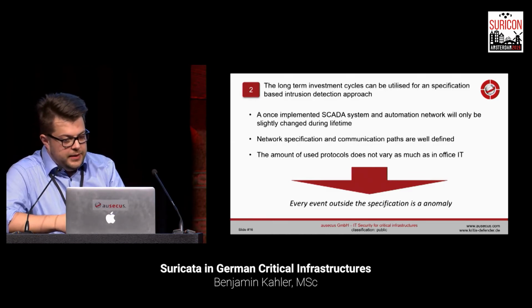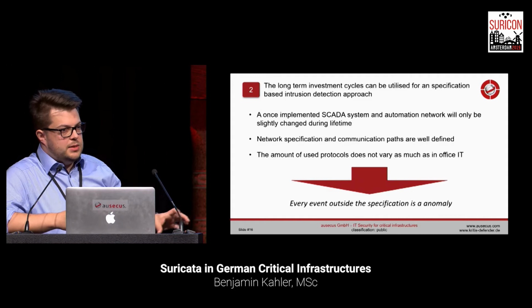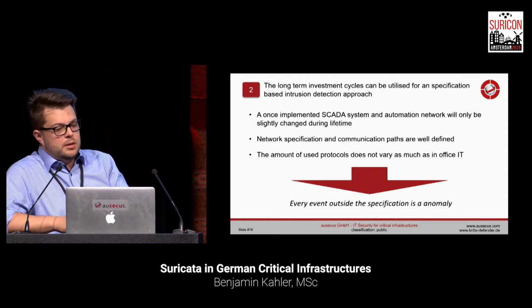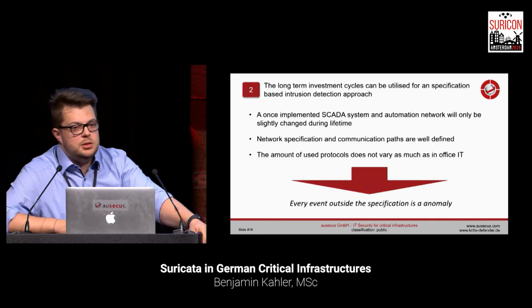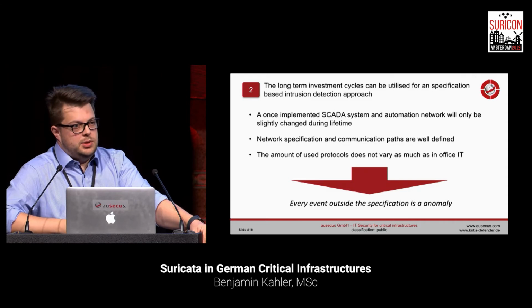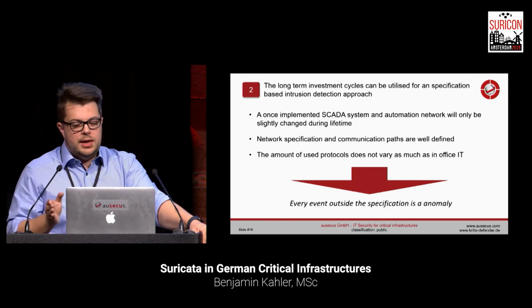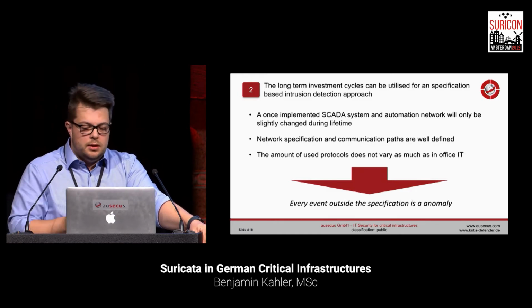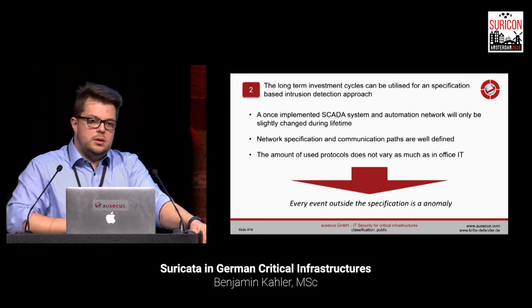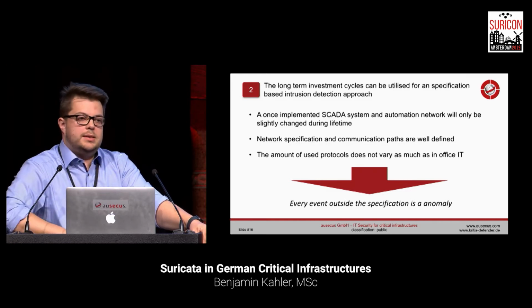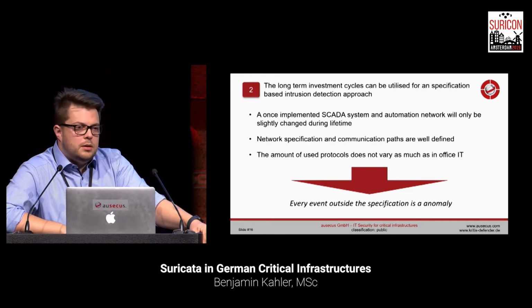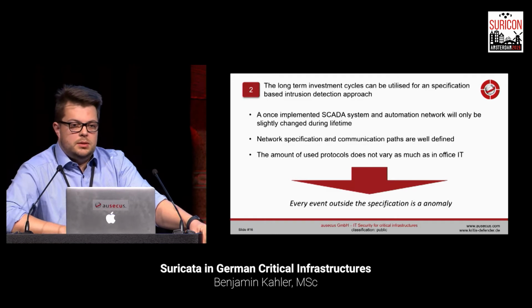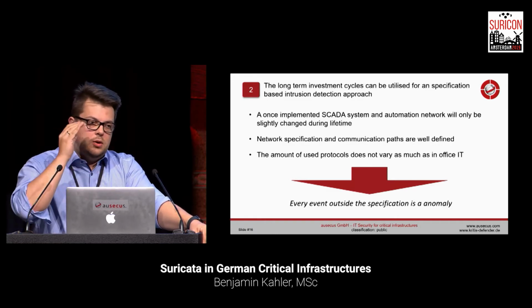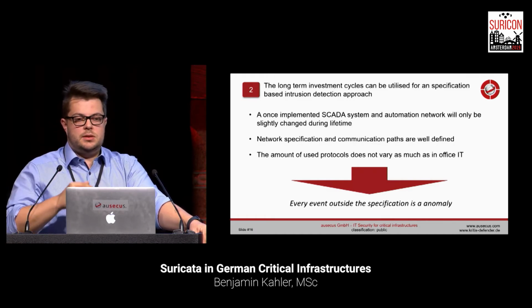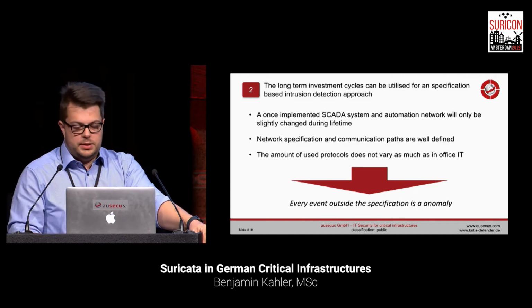Network specification is really fixed, communication paths are really fixed, so we can define rules in our sensors and in our KRITIS Defender like the specification of the network, because it will not change in the next years. Every event outside of the specification is an anomaly, and every event outside of the rules we can call an incident. So we often use negations in rules—if a command is not from the SCADA servers, then that could be an attack.